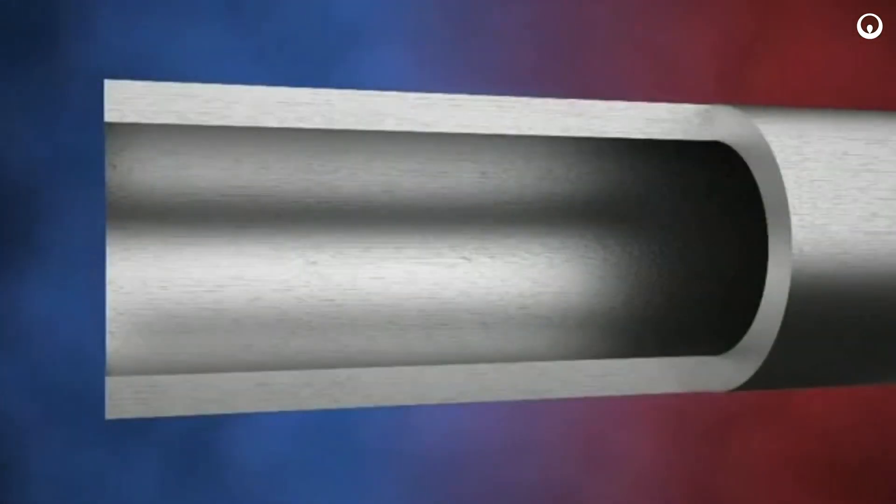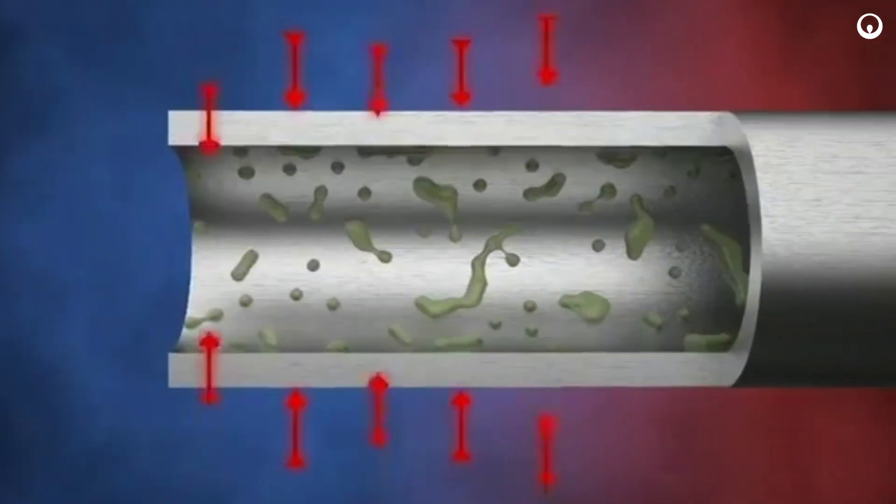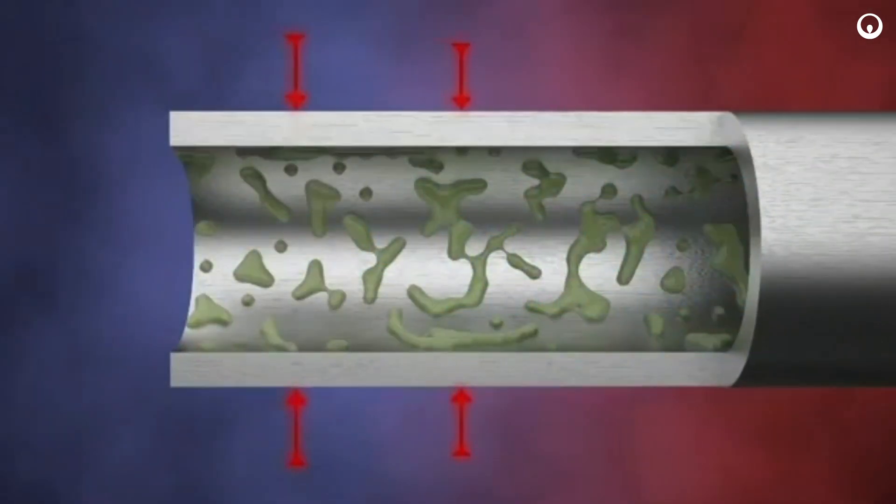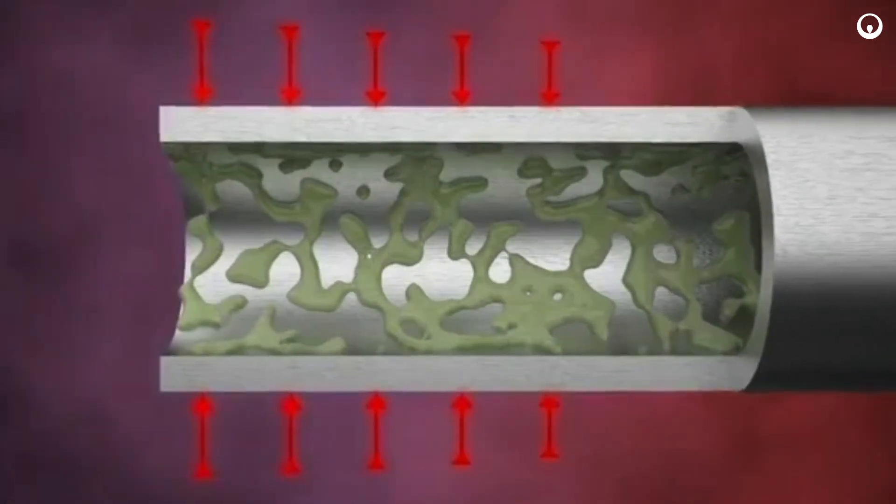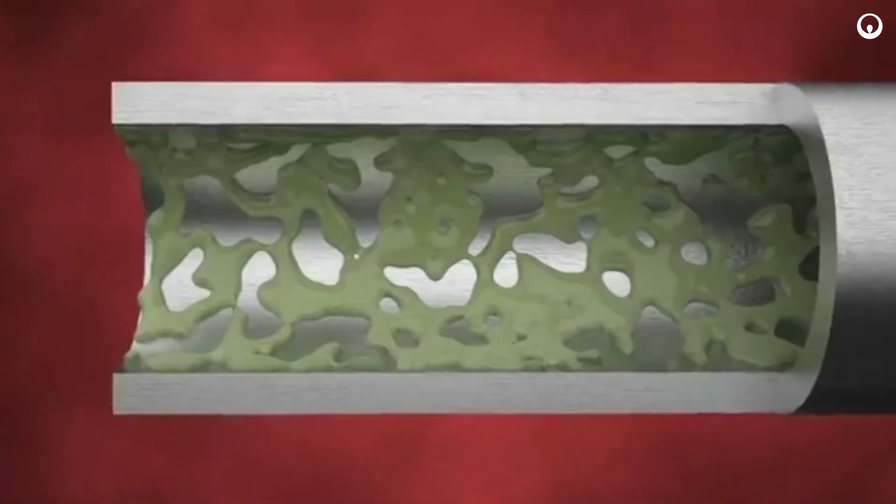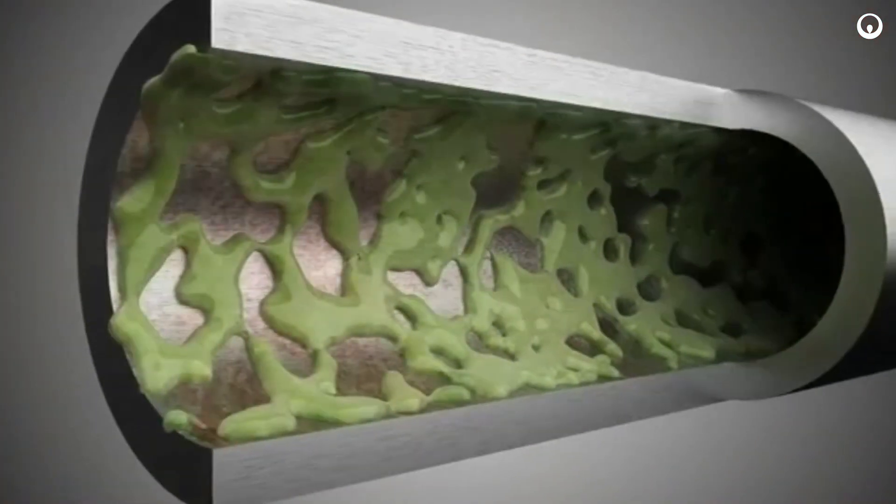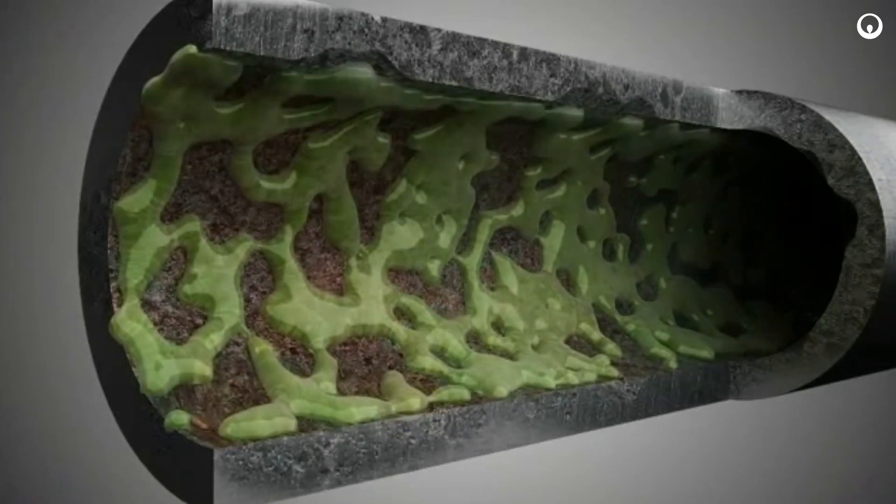When biofilms grow to fouling levels, they reduce cooling efficiency and process throughput. Reduced cooling efficiency due to biofouling can lead to higher energy costs or force unscheduled outages for cleaning. Over time, biofilms also cause equipment damage due to corrosion, which can increase maintenance and replacement costs.